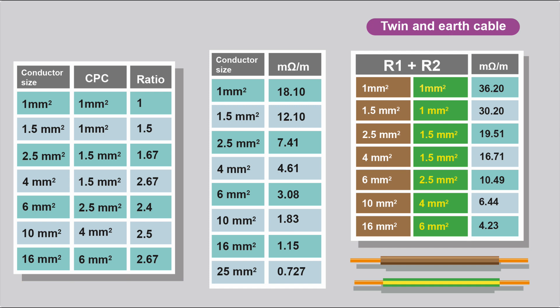We've got three tables here, which you would use for your twin-and-earth, the first table. We've got the conductor size, this would be the live or the neutral, and this is the CPC. In twin-and-earth, the line and neutral cable is the same cross-sectional area. The CPC is different, so there's the ratio.